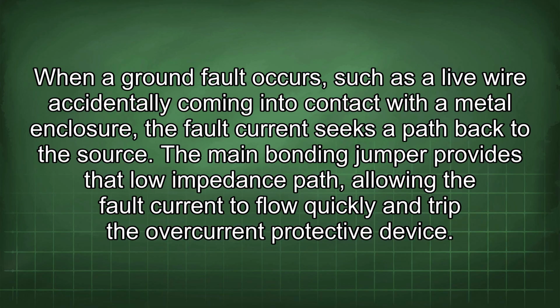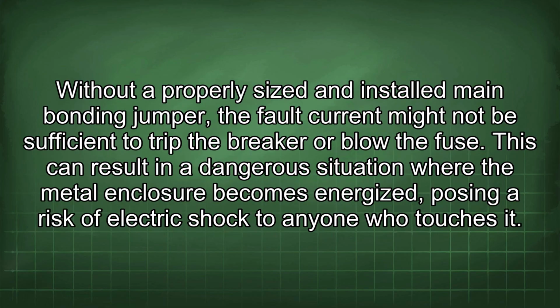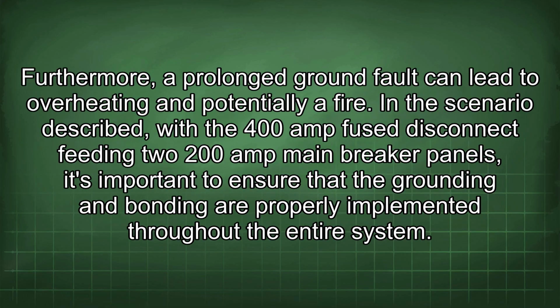When a ground fault occurs, such as a live wire accidentally coming into contact with a metal enclosure, the fault current seeks a path back to the source. The main bonding jumper provides that low impedance path, allowing the fault current to flow quickly and trip the overcurrent protective device. Without a properly sized and installed main bonding jumper, the fault current might not be sufficient to trip the breaker or blow the fuse. This can result in a dangerous situation where the metal enclosure becomes energized, posing a risk of electric shock to anyone who touches it. Furthermore, a prolonged ground fault can lead to overheating and potentially a fire.